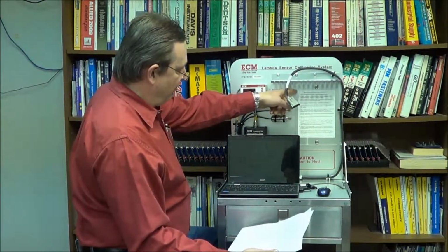The Lambda sensor operates on the diffusion principle. As such, you can calibrate it in a single gas. Air is the easiest to use. Due to the sensor design, there is no zero drift, but there can be a span drift, so the calibration simply consists of a span in air, which we call span O2. I'll go through the procedure to use the calibration system by following what's written here.